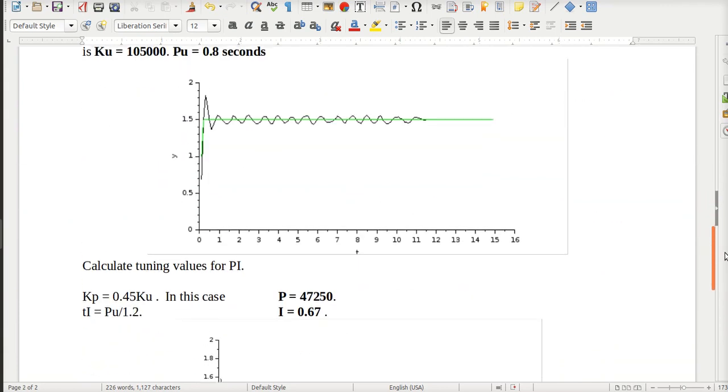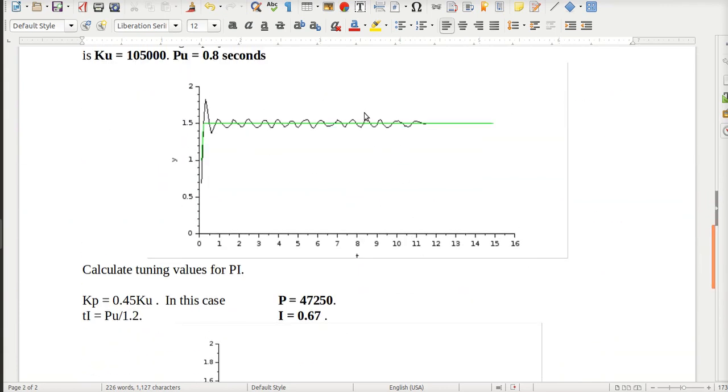But incidentally, when controllers auto tune, they do something that is like this closed loop. They're looking for oscillations in the process, and since they're mathematically doing it, they don't have to see a lot of data to see what happens. They can see how the graph's going in real time, so they can tune very quickly.